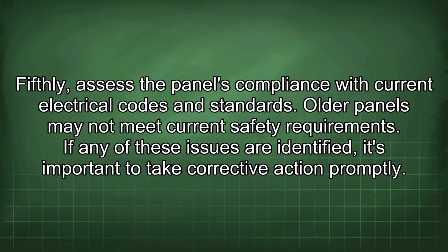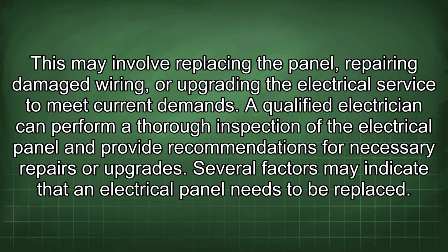Fifthly, assess the panel's compliance with current electrical codes and standards. Older panels may not meet current safety requirements. If any of these issues are identified, it's important to take corrective action promptly. This may involve replacing the panel, repairing damaged wiring, or upgrading the electrical service to meet current demands. A qualified electrician can perform a thorough inspection of the electrical panel and provide recommendations for necessary repairs or upgrades.